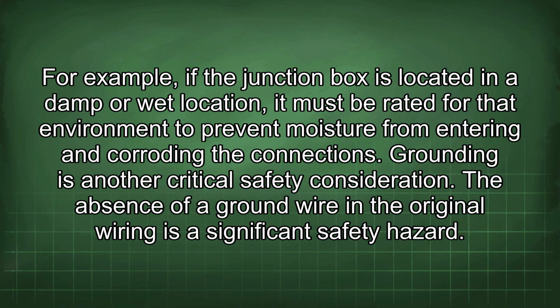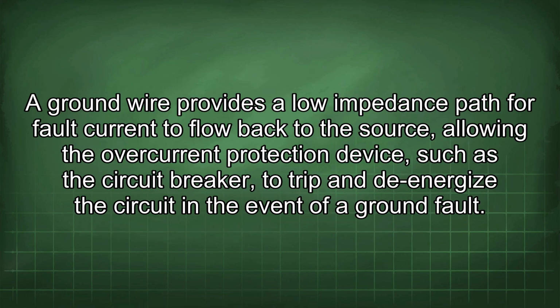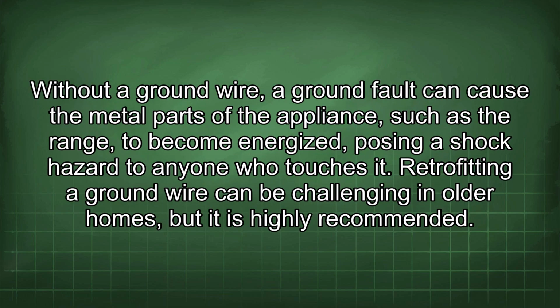Grounding is another critical safety consideration. The absence of a ground wire in the original wiring is a significant safety hazard. A ground wire provides a low impedance path for fault current to flow back to the source, allowing the overcurrent protection device, such as the circuit breaker, to trip and de-energize the circuit in the event of a ground fault. Without a ground wire, a ground fault can cause the metal parts of the appliance, such as the range, to become energized, posing a shock hazard to anyone who touches it.